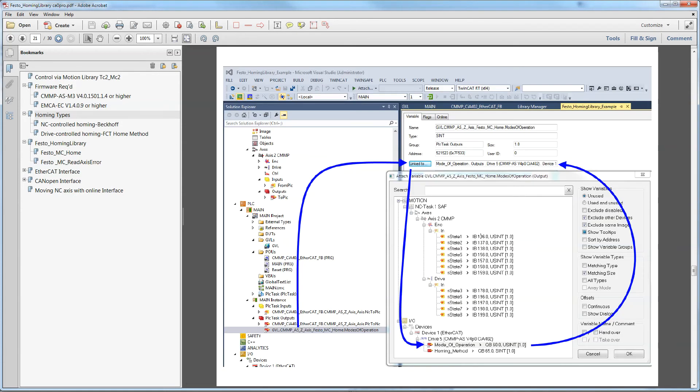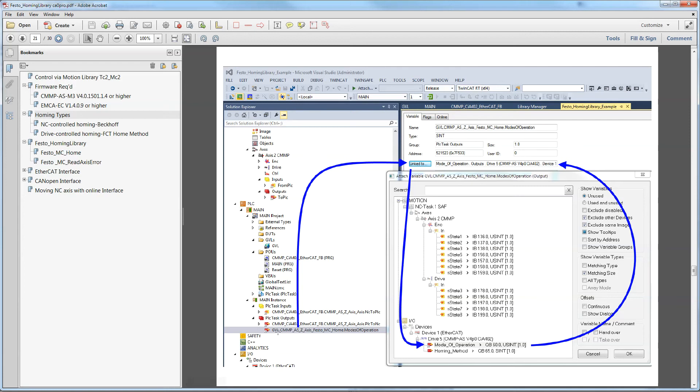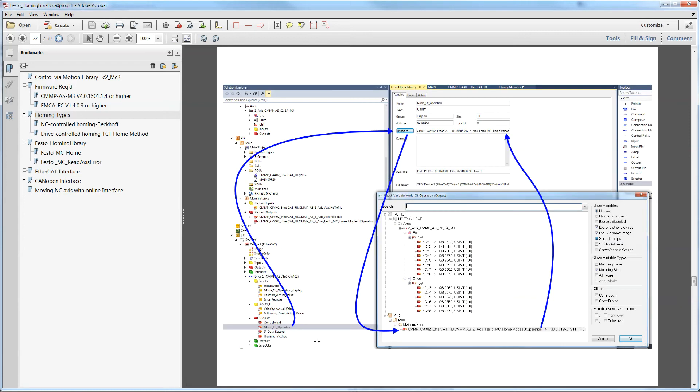Inside my PDF I added this right here, so this is what it means by linking the modes of operation manually to the drive. I've given you two perspectives here, one from the top view and one from the bottom view. You need that modes of operation in order to send the SDO, in order to execute the SDO which changes the mode of operation during the process of the function block actions.